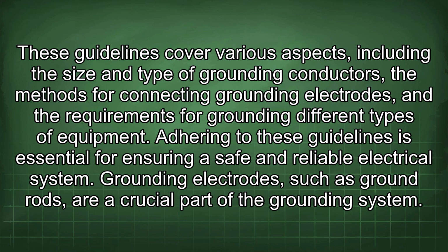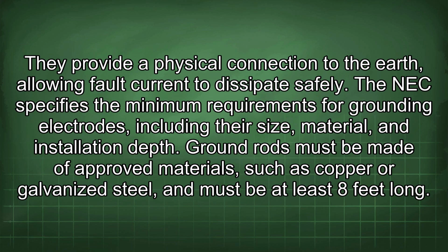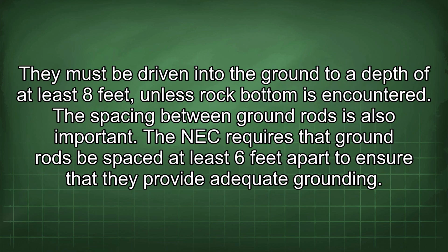Grounding electrodes, such as ground rods, are a crucial part of the grounding system. They provide a physical connection to the earth, allowing fault current to dissipate safely. The NEC specifies the minimum requirements for grounding electrodes, including their size, material, and installation depth. Ground rods must be made of approved materials such as copper or galvanized steel and must be at least 8 feet long. They must be driven into the ground to a depth of at least 8 feet unless rock bottom is encountered. The spacing between ground rods is also important.